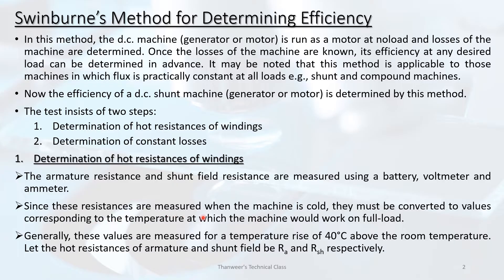Since these resistances are measured when the machine is cold, they must be converted to values corresponding to the temperatures at which the machine would work on full load. Cold condition resistances are corrected for a temperature rise of 40 degrees Celsius above the room temperature. Let the hot resistance of the armature and shunt field resistance be R_A and R_SH respectively.